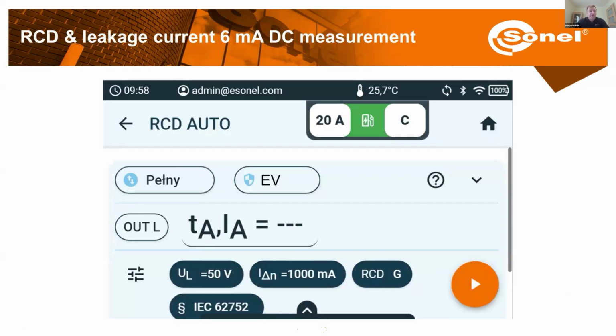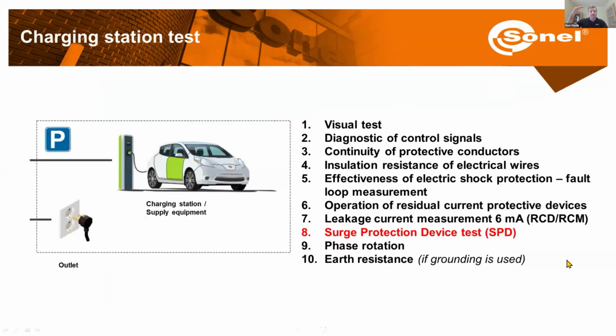Okay, now as it comes to the meter, we can define the automatic RCD tests. So we can select the type of RCD here for the electric vehicle, and we can check the triggering current as well as triggering time for nominal currents times half, 1, 2, 5, 10, 33, or 50 times. So depending on the type of applicable standard, we can perform all of the necessary tests within the meter. And at the end, we will just have a list of the results. It is natural that during the test the RCD is going to trip a few times, which is normal. We just need to put it back on, and the meter will automatically continue the tests.